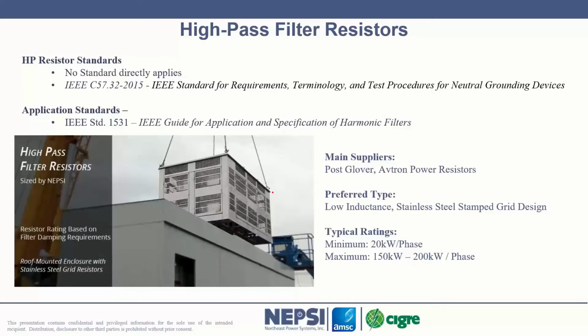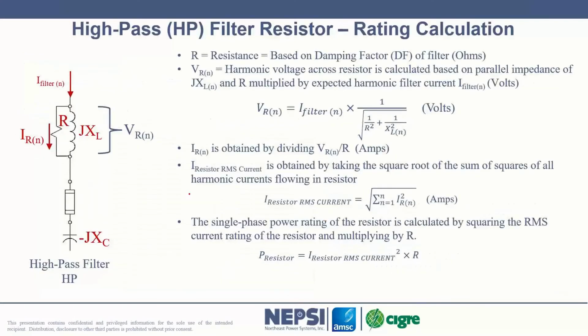So resistors, again, we're putting them on top. Look for low inductance. We prefer a stainless steel stamped grid design. We typically see ratings no more than, say, 200 kW, and we're closer, I think, to 150, 180, 200 kW per phase. You think about it, there's a lot of losses in a resistor. The resistors go inside an enclosure like this. It's well ventilated. We prefer not to use any forced cooling in the design.